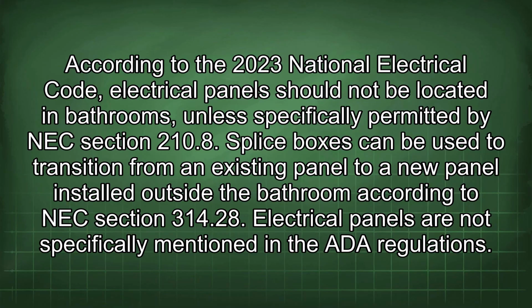According to the 2023 National Electrical Code, electrical panels should not be located in bathrooms unless specifically permitted by NEC Section 210.8. Splice boxes can be used to transition from an existing panel to a new panel installed outside the bathroom according to NEC Section 314.28. Electrical panels are not specifically mentioned in the ADA regulations.